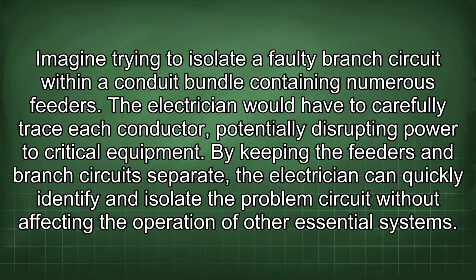Imagine trying to isolate a faulty branch circuit within a conduit bundle containing numerous feeders. The electrician would have to carefully trace each conductor, potentially disrupting power to critical equipment. By keeping the feeders and branch circuits separate, the electrician can quickly identify and isolate the problem circuit without affecting the operation of other essential systems.